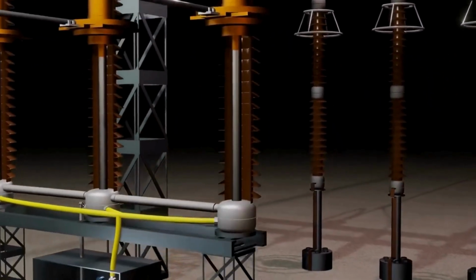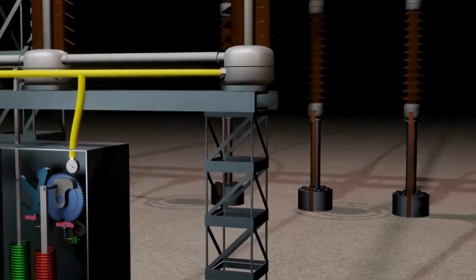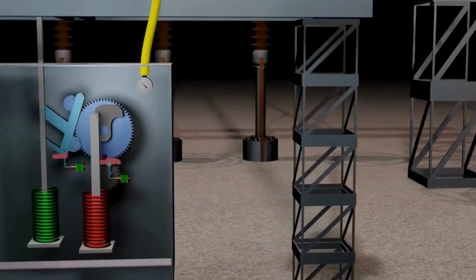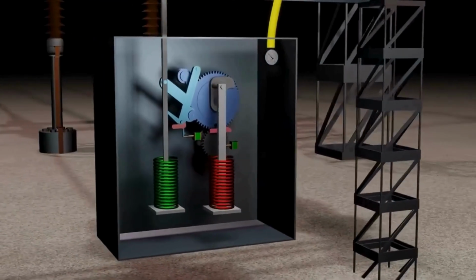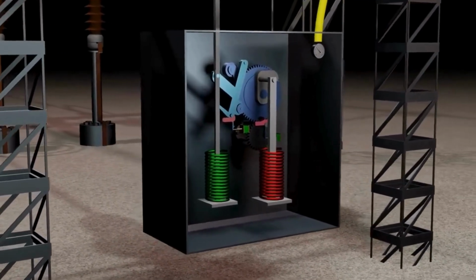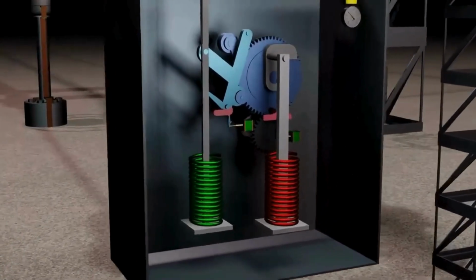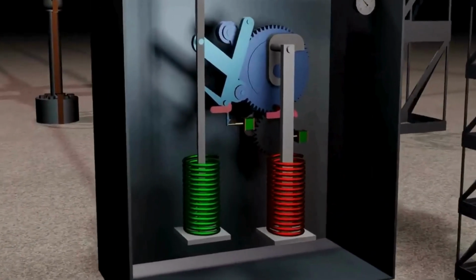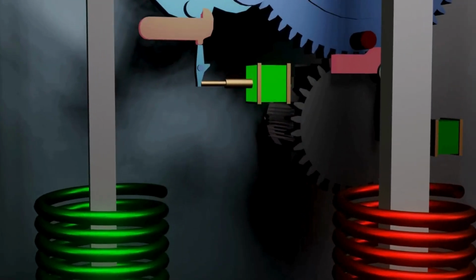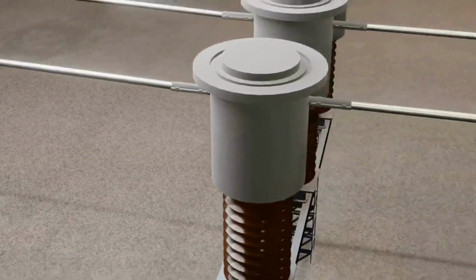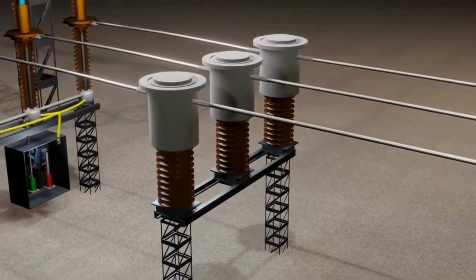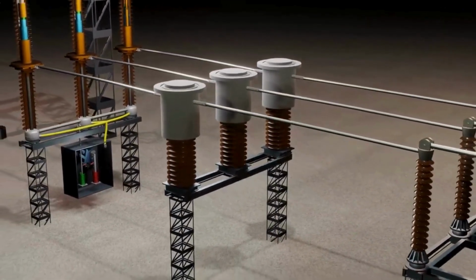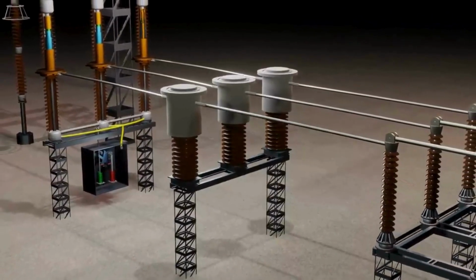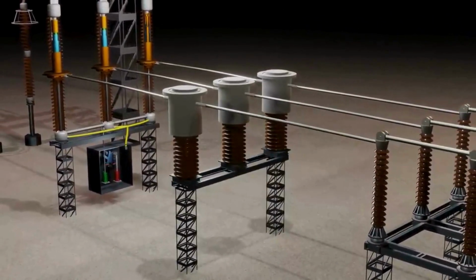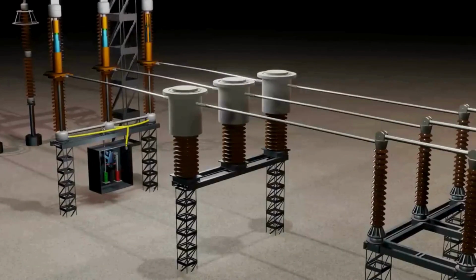Let's assume that the line is on and the circuit breaker is in contact. There are two conditions here. If there is a fault in the line or we manually open the circuit breaker, then the line breaks in both the conditions in the same process. This mechanism has two springs and both the springs are loaded. Below is a relay with the plunger system. A current transformer is also installed near the circuit breaker. So whenever there is a fault in the line, high current will flow from the current transformer. And the current transformer tells the relay that more current is flowing than normal, so the breaker needs to be tripped.